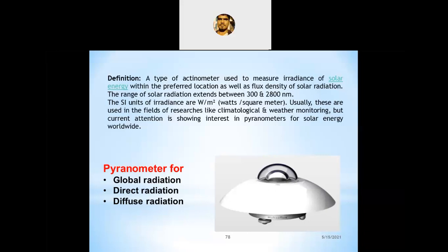And this EMF, which is in the range of 0 to 10 microvolts, can be read and recorded, integrated over a period of time, with regular calibration. It means we have to regularly check the device efficiency, and approximately plus or minus 1 to 2 percent is acceptable, okay.